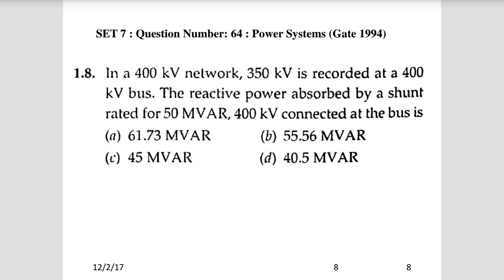Question 64: In a 400 KV network, 350 KV is recorded at the 400 KV bus. The reactive power absorbed by a shunt reactor rated 50 MVAr at 400 KV connected at the bus is to be found. Since the actual voltage is 350 KV instead of 400 KV, the reactive power absorbed will be less than the rated 50 MVAr. We can eliminate choices of 61.73 MVAr and 55.56 MVAr, keeping only options below 50 MVAr.